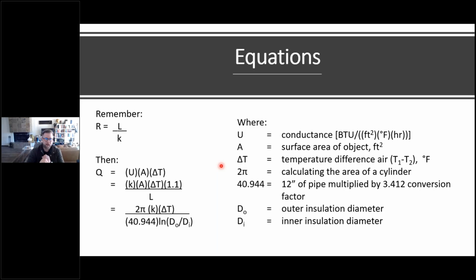Now, we're talking about a pipe, right? Not a flat plate. So in essence, to convert that cylinder to a flat plate, we are going to change the equation slightly by, if in your mind, imagine that you slice down the side of the pipe, and then you're opening up the pipe to make it single direction as opposed to radiating outwards. That's the modification in the equation here. So that's where you get your 2 pi, your 40.944 constants, and then your logarithm of your outer diameter divided by your inner diameter. And again, keeping in mind that your inner insulation diameter is going to be smaller than your outer insulation diameter, just due to the fact that it's going around a pipe. So it's going to be a little bit of a trapezoid if you were to look at it from the side.